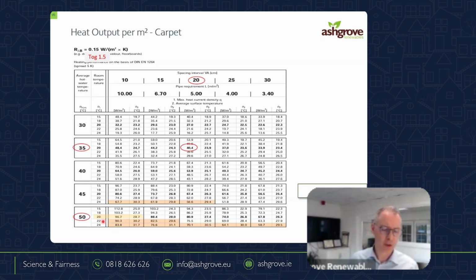Now, if I want 22 degrees, you can see here I'll only get 90 watts out. Either way, what we're actually starting to see here, by the way, what you can see is the floor surface temperature now is creeping away up. We're into this salmon color here, which we call peripheral zone. Peripheral zone is if I have a floor surface temperature that's 30 degrees, within 1 minute, you'll feel that heat through the soles of your shoes. If you have a scenario like that, there's something gone wrong, and it becomes very hard to control it.